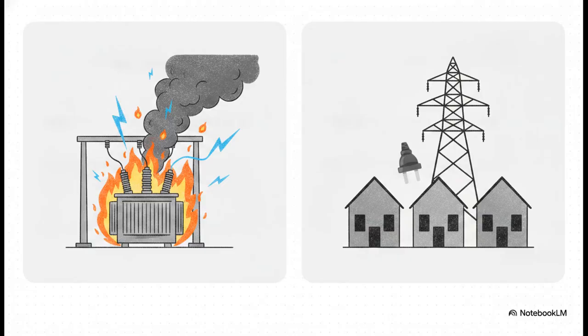Protection engineers live constantly between two extreme, completely opposite failure modes. Picture this. On one hand, a relay fails to trip during a real fault. What happens? Equipment burns, breakers spark, and catastrophic damage just spreads across the substation. On the other hand, you've got the exact opposite nightmare. A relay trips falsely during normal operation. It essentially detects a phantom issue and needlessly blacks out a perfectly healthy section of the grid, leaving customers who did nothing wrong in the dark. Every single protection design decision on the grid is a massive trade-off between these two risks.